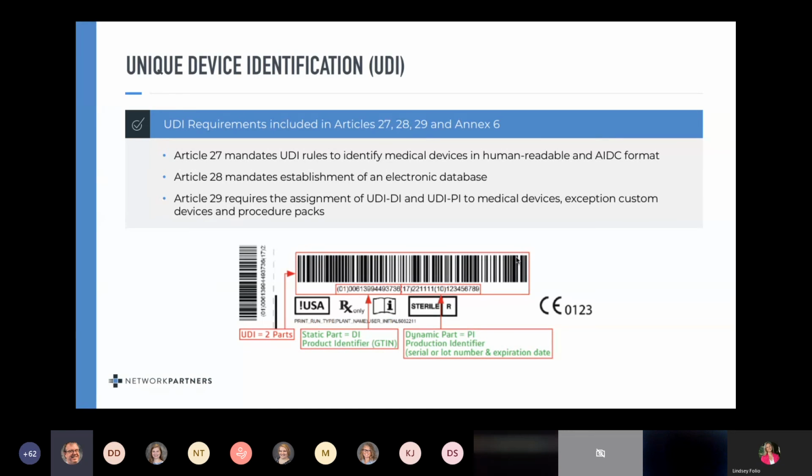And I'm going to mention one thing that could have a big impact on your plans. What the industry, we talk to a lot of clients, is going towards is using the patient implant card, using the symbology that's in 15223, and then pointing the patient on their patient implant card to the patient information website and not putting pre-printed patient information into the package.